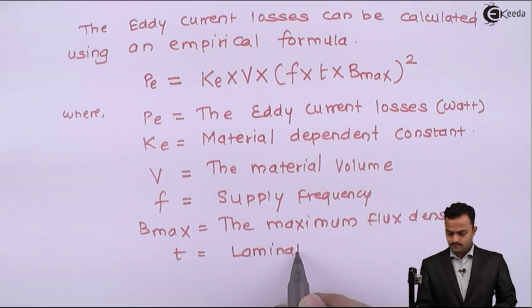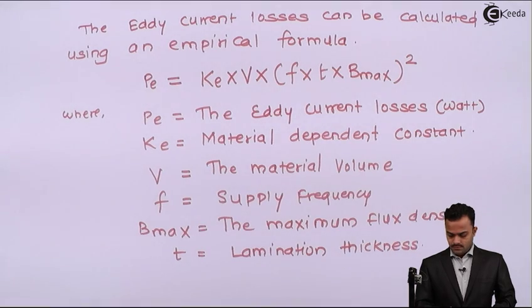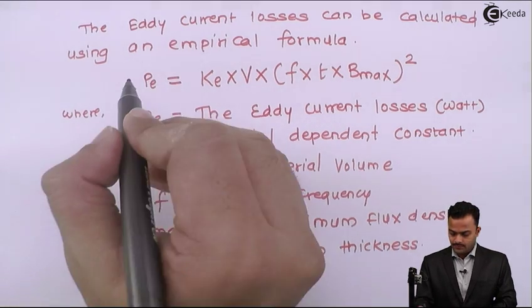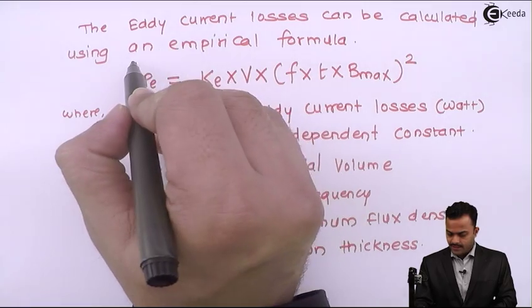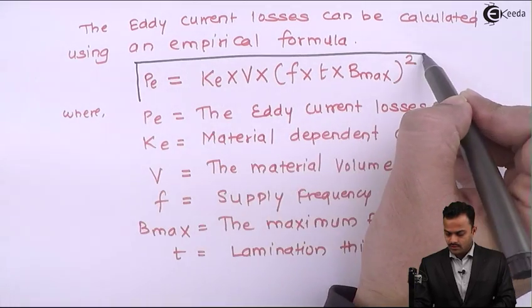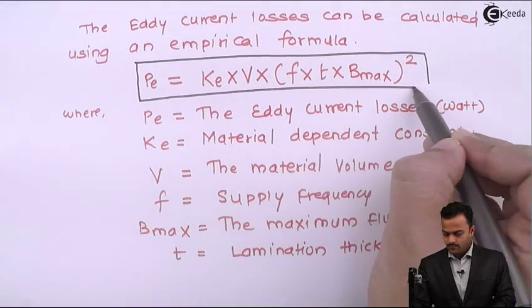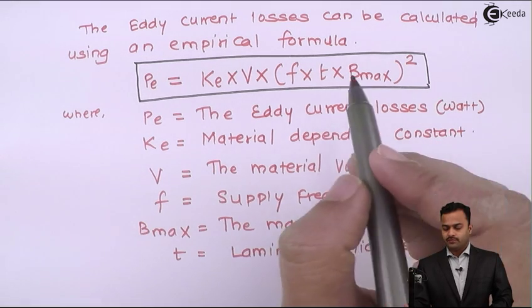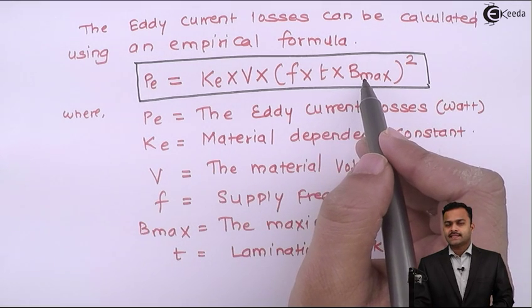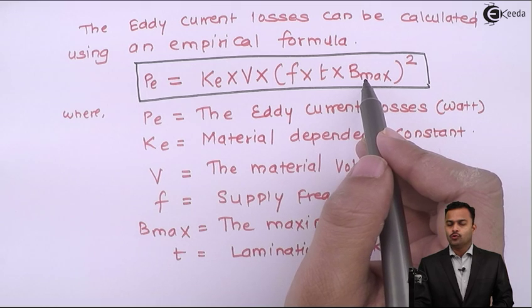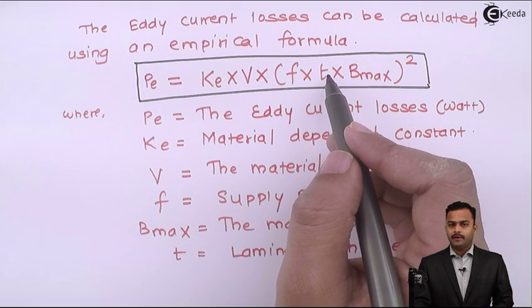So if you see the formula once again, you will come to know that eddy current loss depends on square of the frequency, maximum flux density, and most important, lamination thickness.